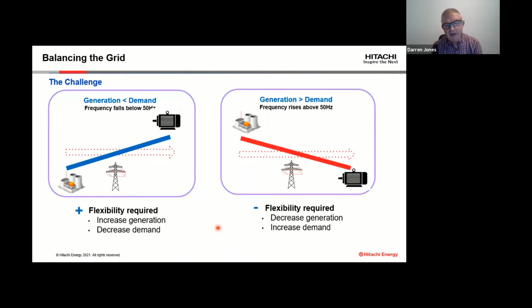The last major system event we had in the UK was in August 2019 down in the southeast. There was a lightning strike to a couple of overhead lines that were connecting some of the offshore wind out on the east coast. I think the lightning strike took the overhead line out, which meant that the wind farms were disconnected from the system. There are plenty of reports available if anybody really wants the detail, but there was also a case where some of the standby generators that were supposed to connect to the system and meet the shortfall in generation failed to activate or operate at that time. That then caused frequency to fall, because we didn't have enough generation to meet the demand that was connected.